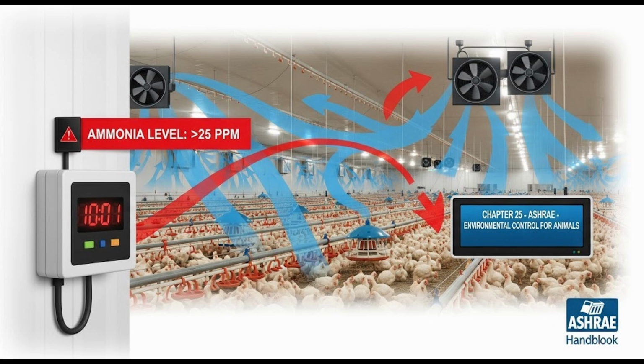And engineers actually calculate how the air flows through those inlets. Yes, there's a method called the system characteristic technique. The handbook gives the formulas. For example, one shows how the airflow rate, Q, through a simple slot inlet depends on the slot width, W, and the pressure difference, P, across it, something like Q is proportional to W times the square root of P. You use these calculations to match the fans to the inlets and the building's leakage. So you know how much air you're actually getting through the planned openings.